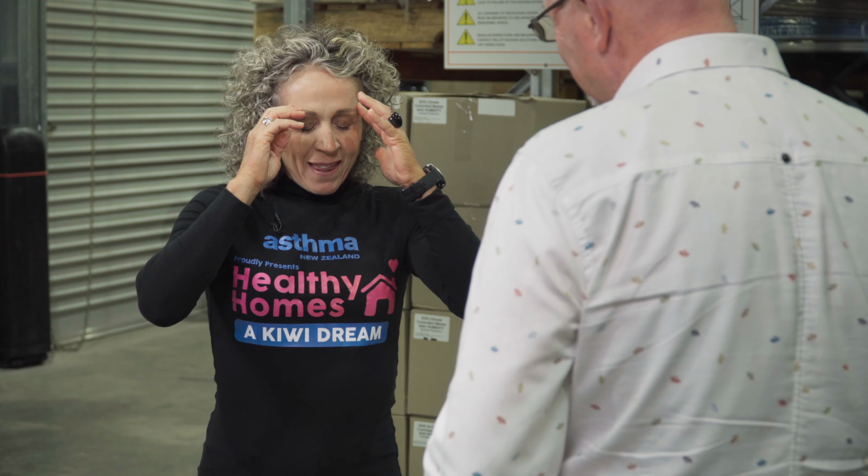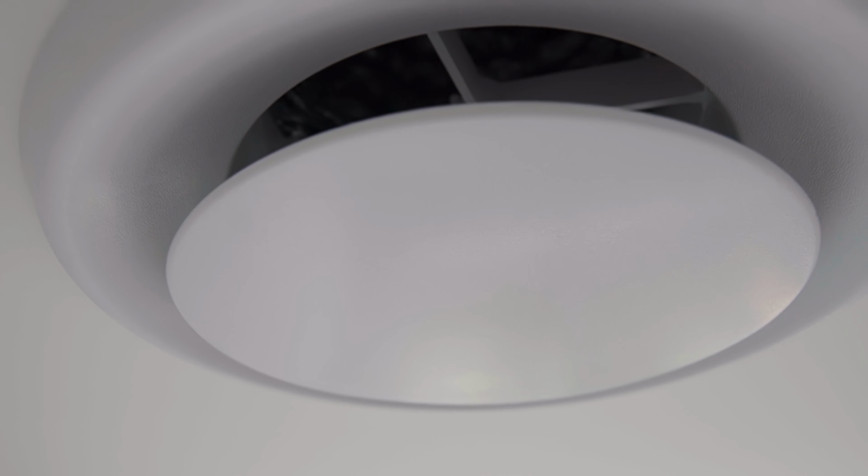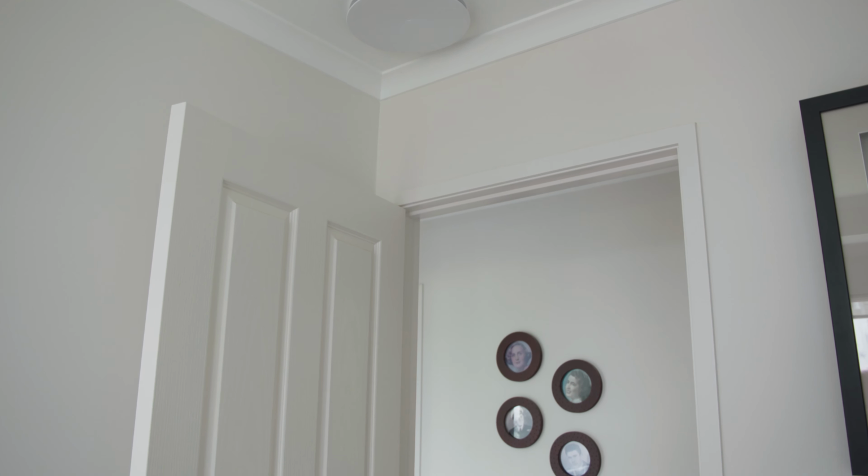Internationally, 35 to 50% of the air in the home is replaced in an hour. That is considered about the sweet spot for a healthy home. In other words, to retain the health of the occupants of the home, and also from an energy efficiency point of view. Yes. The positive ventilation system, the thing I keep stumbling over with that is the fact that you can suck air from the ceiling cavity. And in my mind, I've never spring cleaned my ceiling cavity, so it feels like you're just pushing air down into the living space with a dusting of dirt.